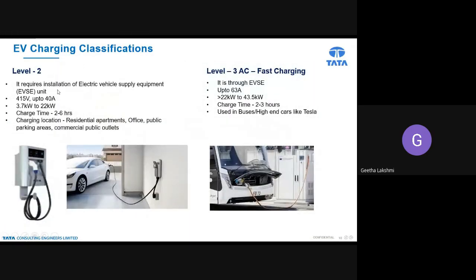Level 2 is the next level up from the slow chargers like level 1. It requires installation of electric vehicle supply equipment (EVSE), with voltage at 230 or 415 volts, up to 40 amps, power range of 3.7 kilowatt to 22 kilowatt, and charge time of 2 to 6 hours. In level 1 you can charge at a residence or office using a simple 230 volt socket, but here you need an EVSE.